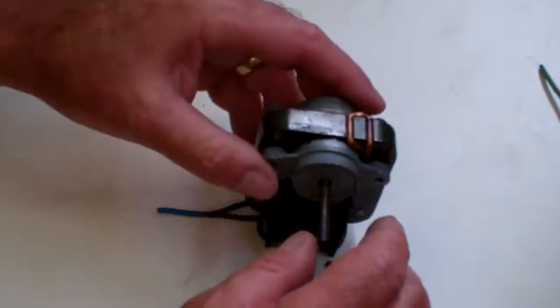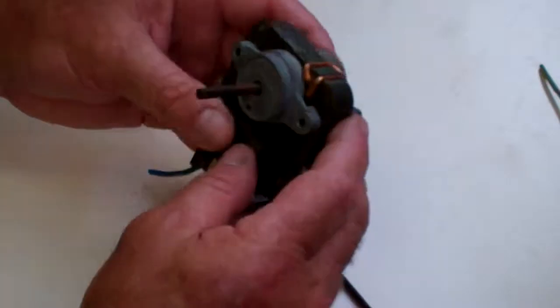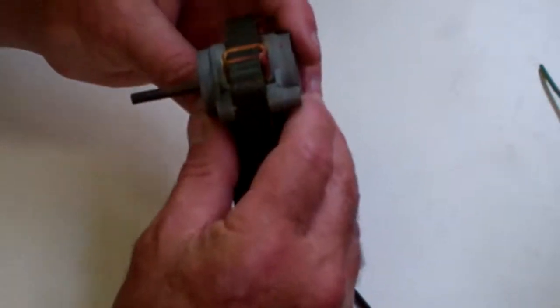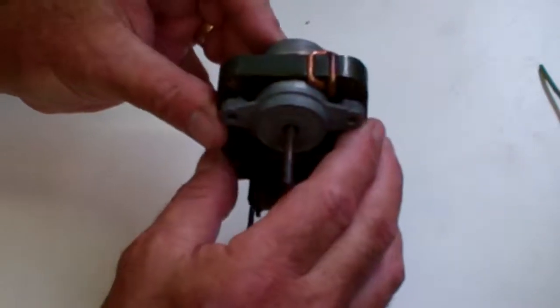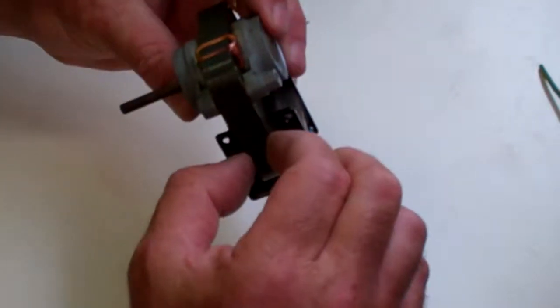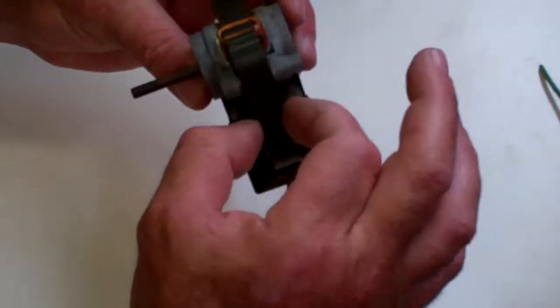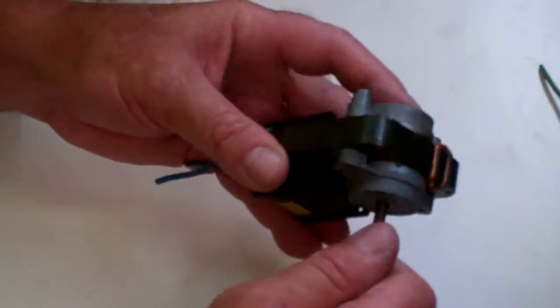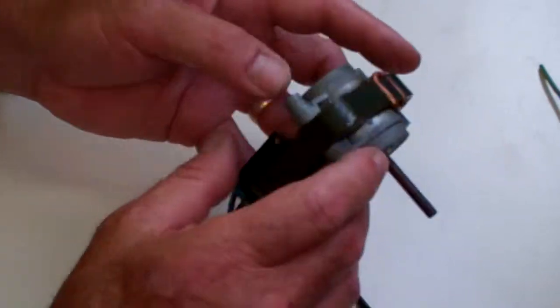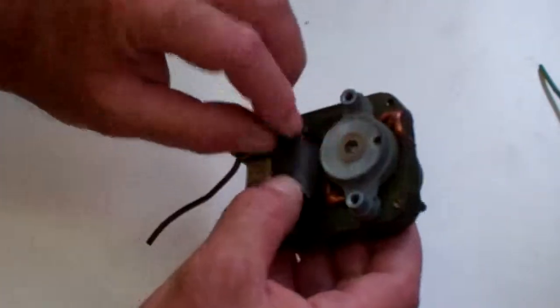The power or the strength of this motor is determined by the thickness of the stack. So if you're replacing one of these motors, make sure the thickness of this stack is identical or greater than the thickness of the stack that you're replacing. Otherwise it won't have enough power to turn the load and it will eventually overheat and the bearings will be damaged.